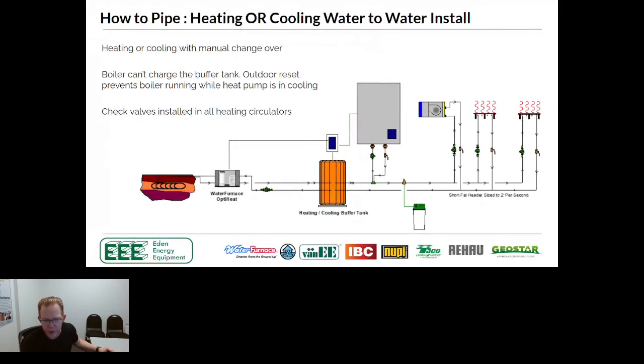Be careful here. If this is a heating and cooling application, just be aware that you've got an air handler down here and you've also got 2 radiant floor systems. You cannot fill chilled water into a slab. It is a bad idea. You can do it, but there's a lot that goes into it. So it's really, really important that whatever our control strategy is, and we're going to show you one in our lab, you make sure you're not dependent on the homeowner. What I mean by that is a suitable answer is not, it's no big deal, Mike, because in the summertime, these 2 radiant floors will never heat. How do you know that? Right?